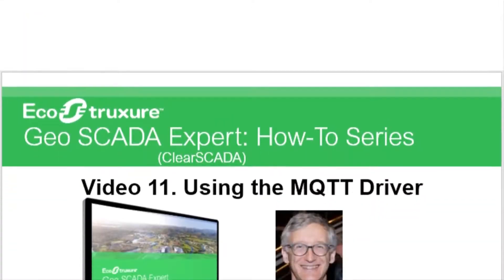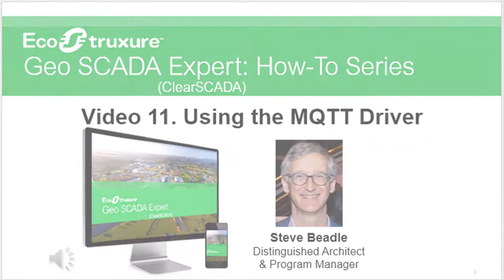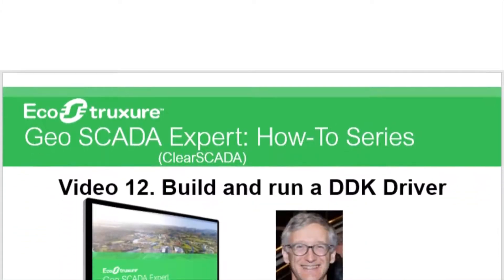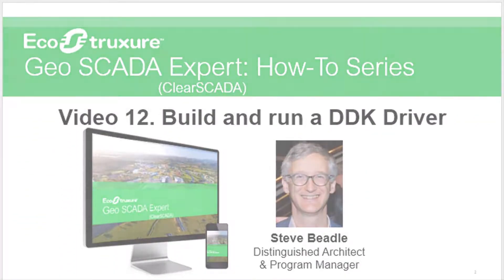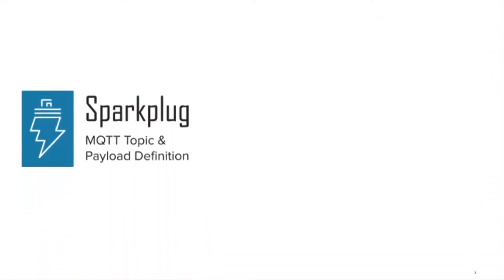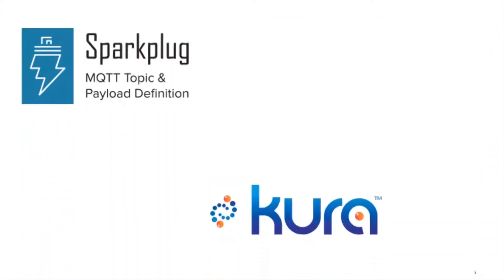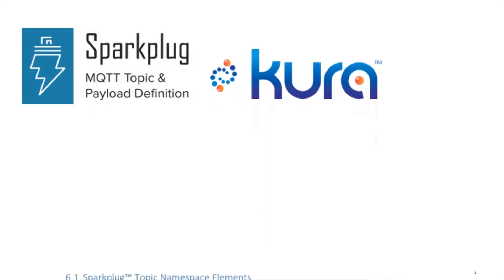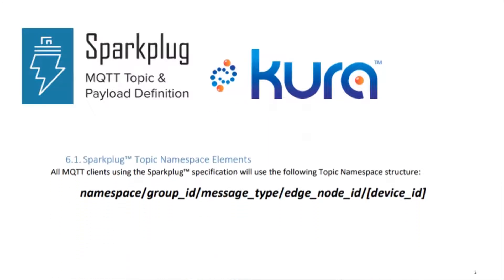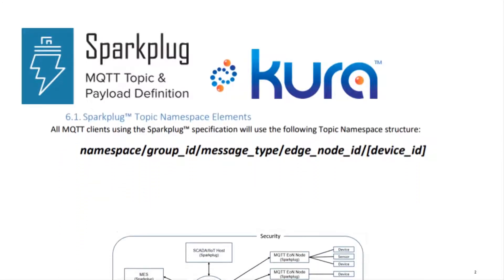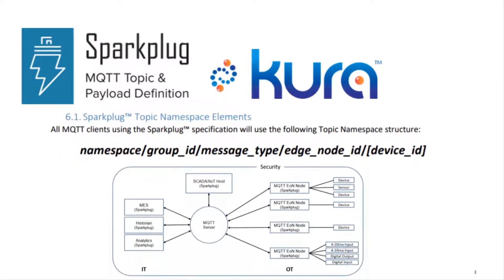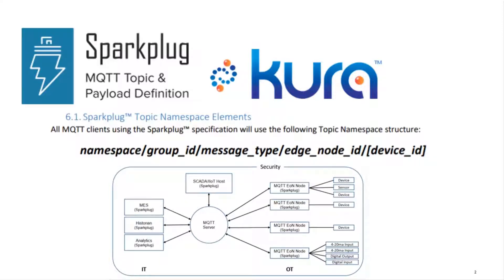This video follows on from the two previous ones for the MQTT and DDK drivers but takes the subject to a new level. Sparkplug B defines a specification for MQTT content that is usable across SCADA and telemetry applications. It uses the binary data format of Google protocol buffers, the structure of Eclipse Kura messaging, and the namespace of Sparkplug B which defines an interoperable SCADA protocol.